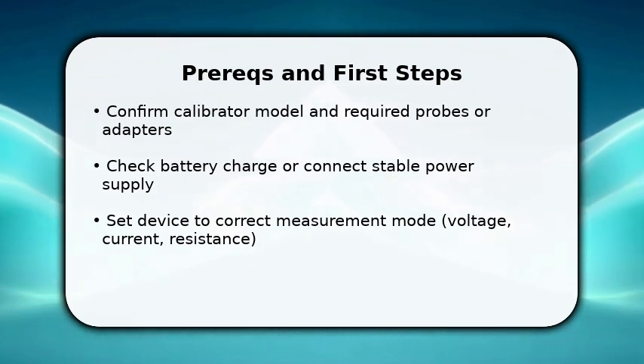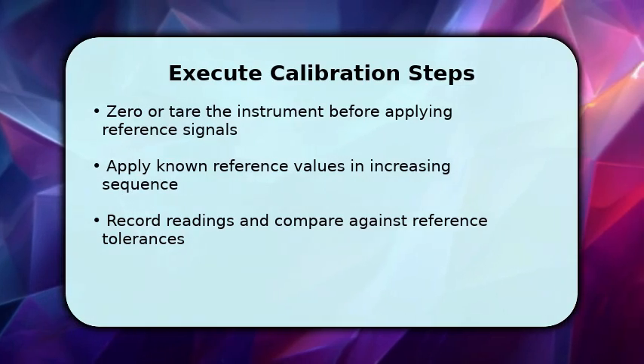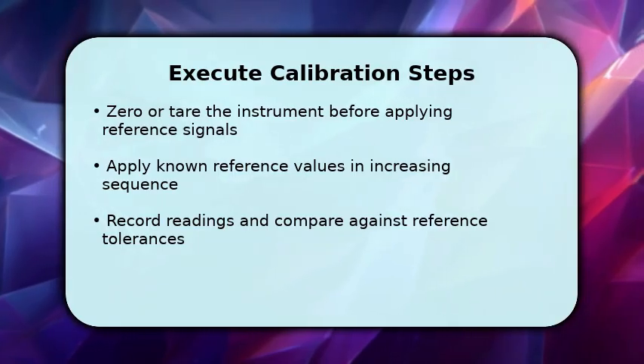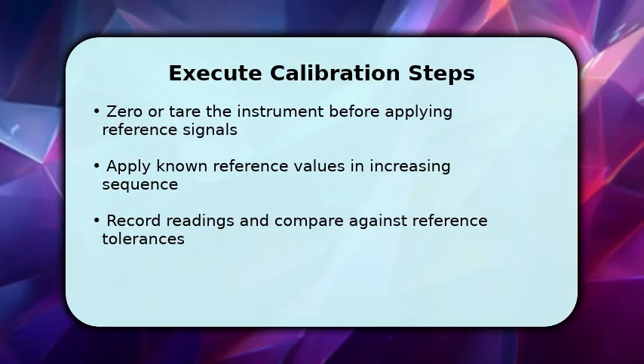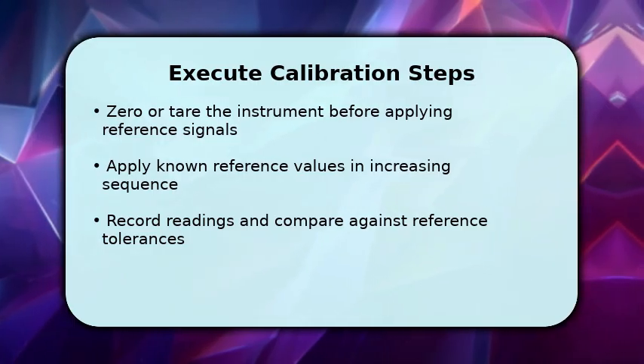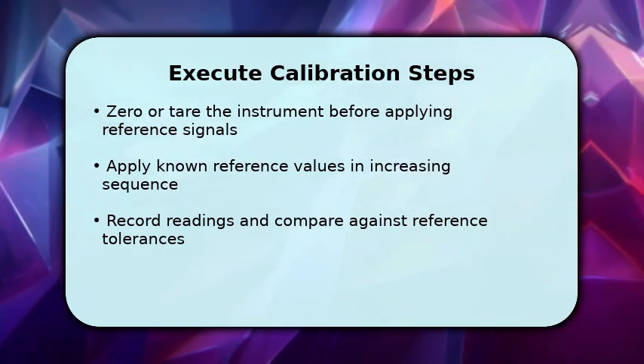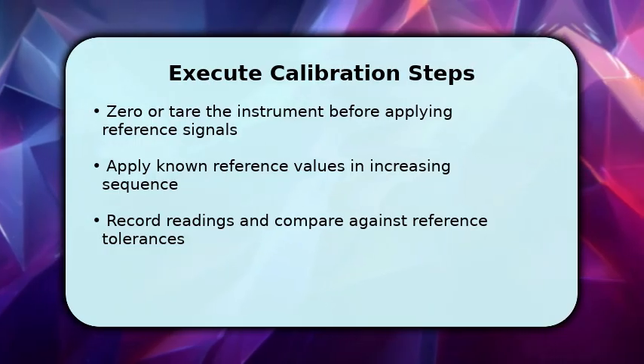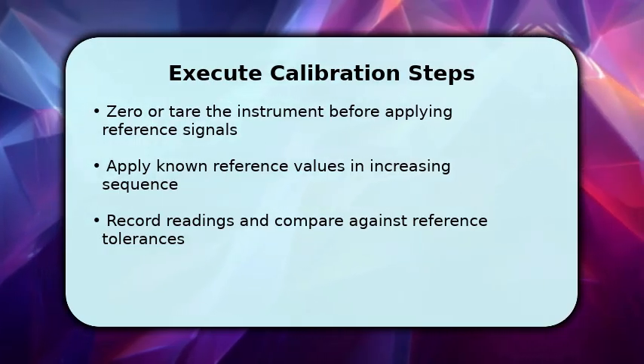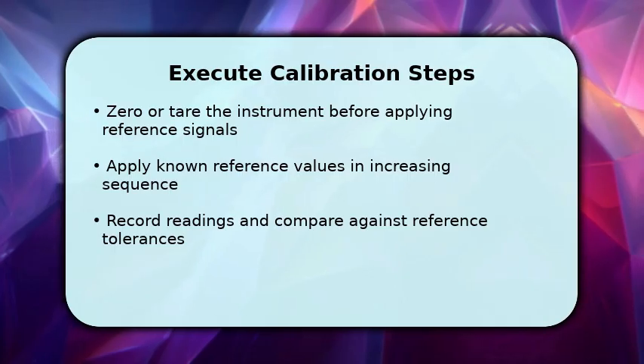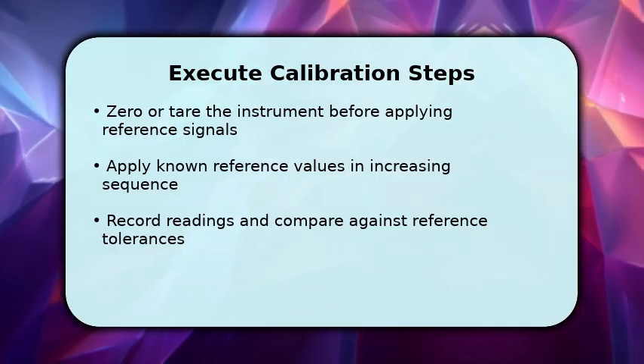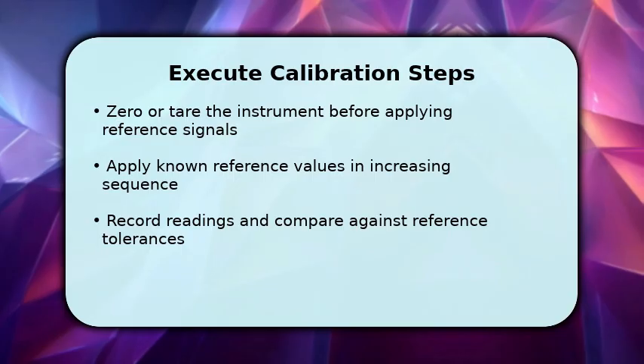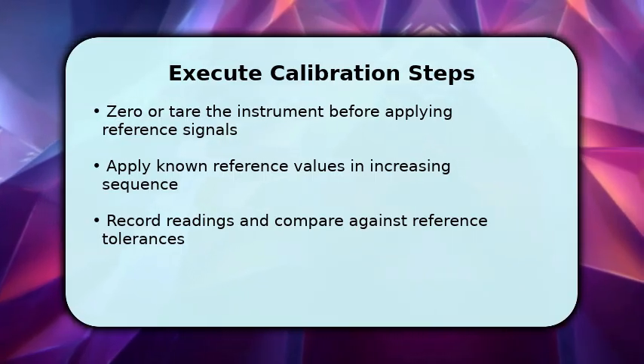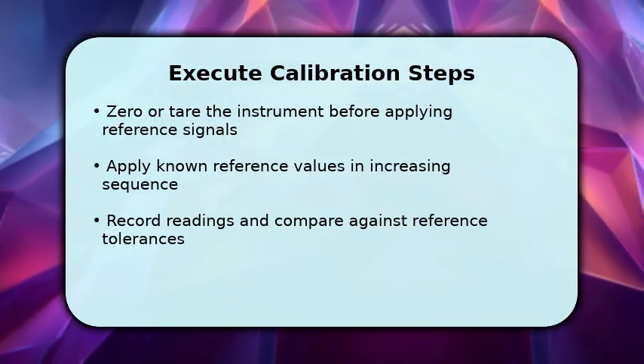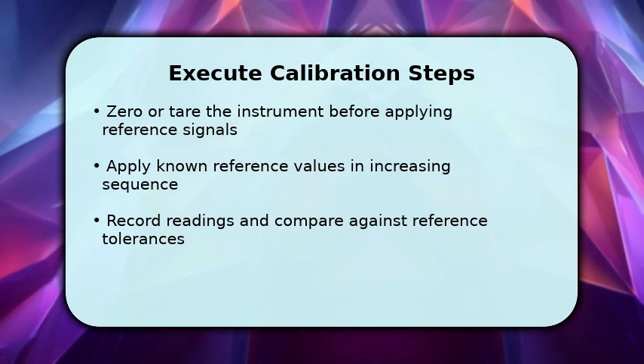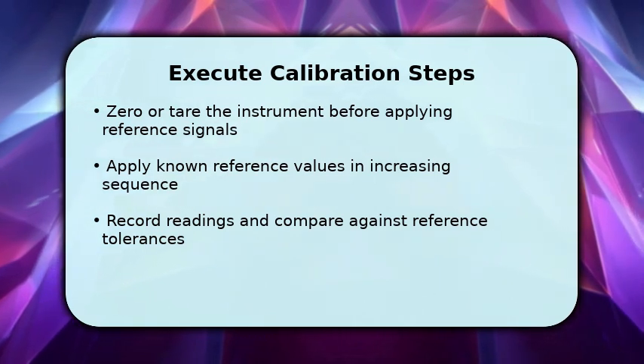You perform the core calibration by first zeroing or taring the instrument under test so offsets don't distort results. Then apply known reference signals or standards in a logical sequence. Start low, move to mid, then high values to reveal linearity or drift. Make sure to let readings stabilize between steps. Rapid changes can hide thermal or settling errors. Record each reading and compute error versus the reference. If values fall inside tolerance, document and move on. If not, note deviation magnitude for adjustment.